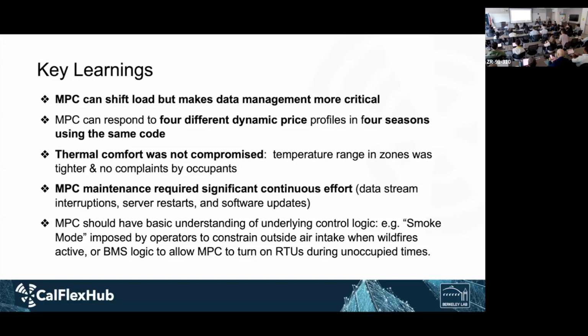To elaborate a bit more, for example, last year when there were wildfires in the summer, the facility managers closed the outside air dampers because they didn't want smoke to enter the building. While I was looking at the results the next morning, I saw that the consumption with the MPC suddenly tripled with respect to what I was expecting, because the MPC was still thinking it could do pre-cooling for free, just running the fans and opening the dampers. But that did not happen. Instead, it was recirculating the air, running the cooling coil at full power.